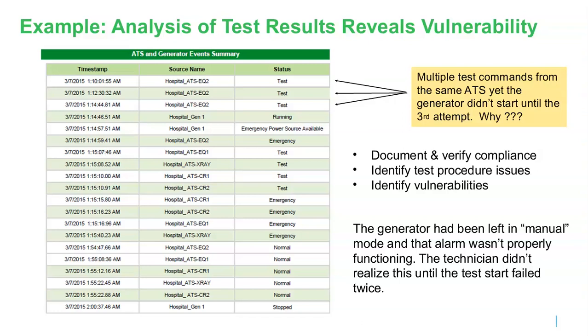And seeing that raised the flag: okay, why didn't the generator start on the first attempt? What was found was that the generator had actually been left in manual mode, and the technicians didn't realize it until minutes later. And the question needs to be asked, well, if it was in manual, what if nobody had noticed for days or weeks later, until there was an actual event?